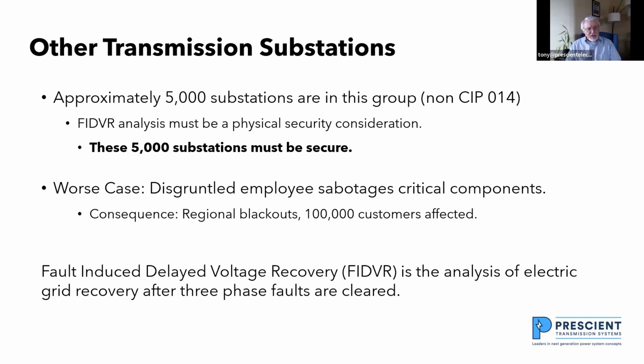So how do I decide what substations really need securing? There's an analysis electrical engineers use called fault-induced delayed voltage recovery, or FIDVR. It looks at a fault that's been on the system for at least 250 milliseconds, and asks whether the grid will respond and return to normal, or collapse. Doing a FIDVR analysis should tell me where my critical transmission substations are.